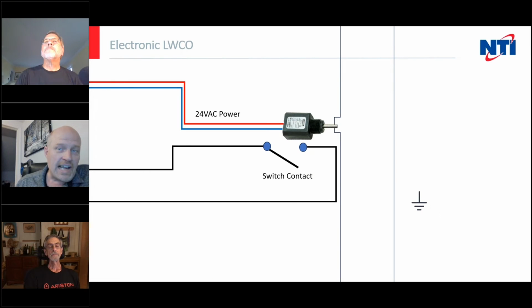There's a switch contact, and on our boilers, I believe we still use just the 2 yellow wires. So if you see the 2 yellow wires on the low water cutoff, at least on the TFT series, we don't use it on the LX. You can actually jumper the 2 yellows if you think you have a bad low water cutoff.